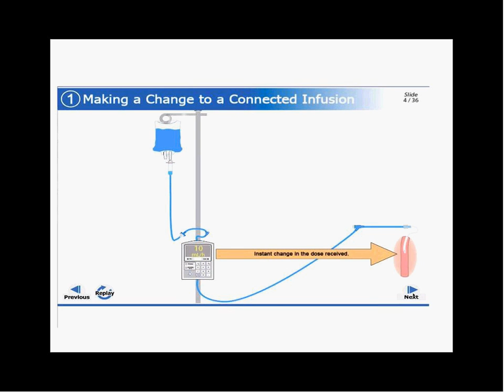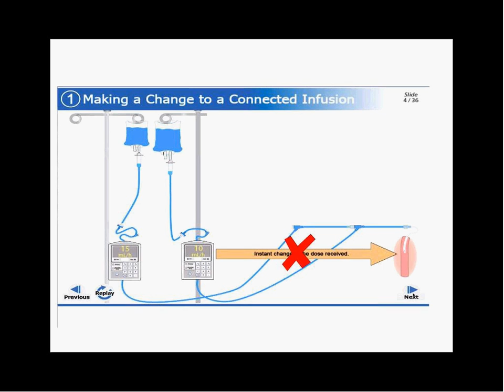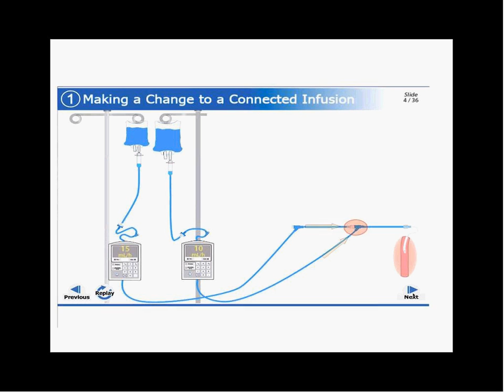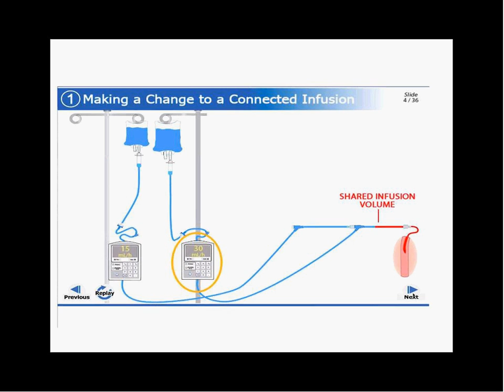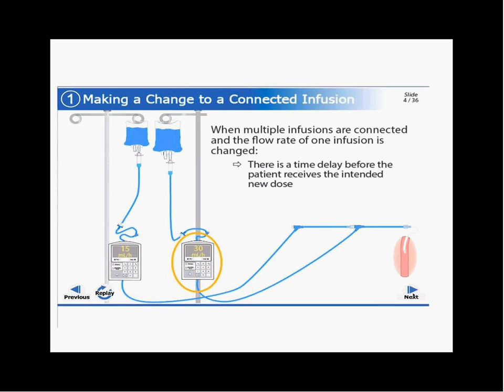But when multiple infusions are connected together, the pump functions and changes are immediate within the tubing, but only up to the point where the infusions join. That join creates an infusion volume for the tubing to carry 2 fluids at the same time. And a change made to one infusion needs to process through this infusion volume before it's received by the patient's bloodstream. So, when multiple infusions are connected and the flow rate of one infusion is changed, there's a time delay before the patient receives the intended new dose.